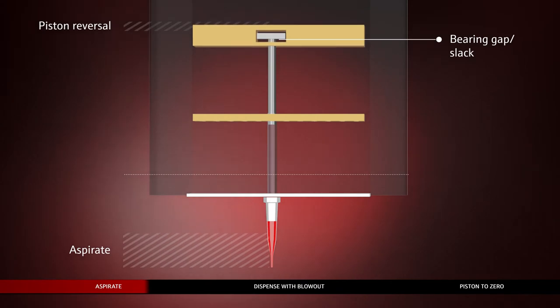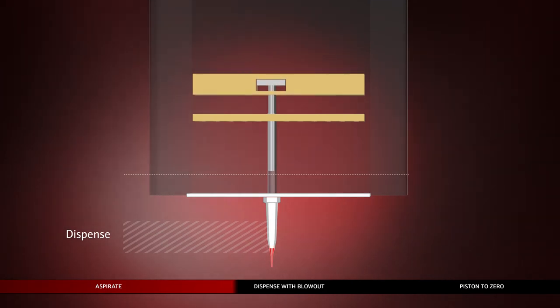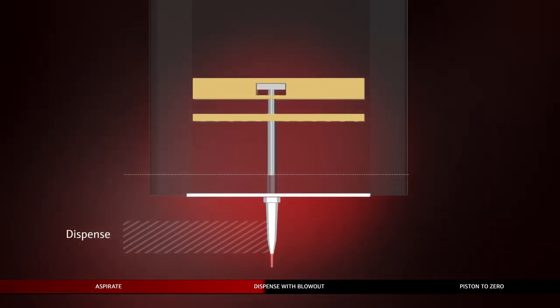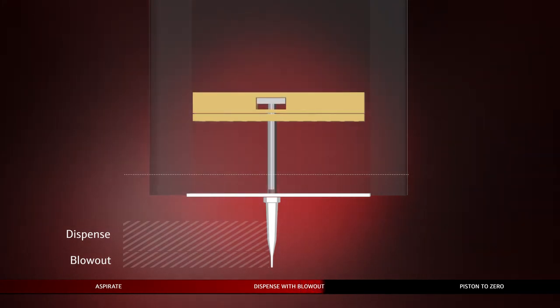During the dispense step, the piston is moved downward. The dispense with blowout is performed into the target well to drain the tips completely and to guarantee the aspirated volume.